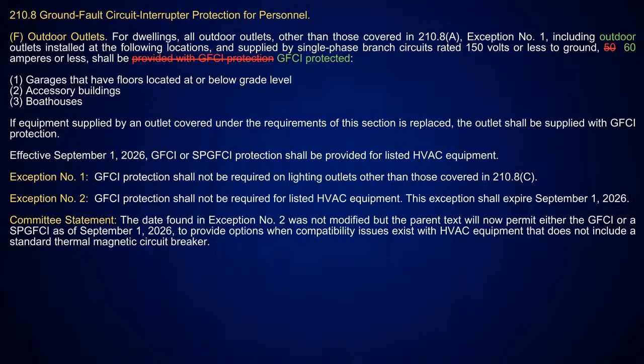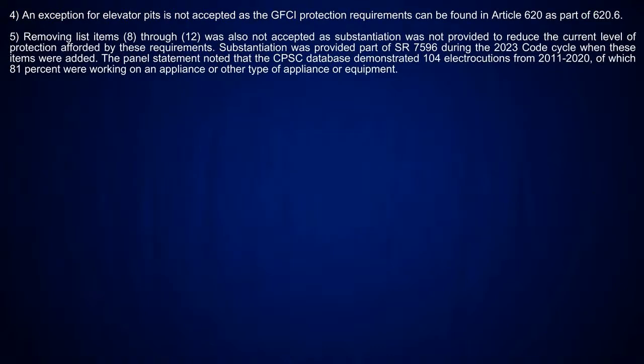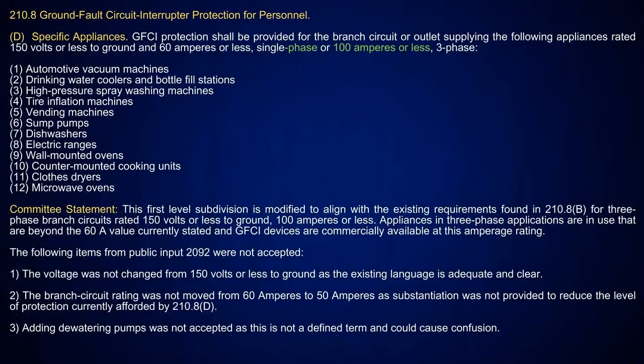So if you go back to that last slide, look at the drinking water cooler and bottle fill stations. So if this is in chapter 2, this is supposed to be protecting the branch circuit. But then all of a sudden you get your drinking fountain water cooler bottle fill stations, and they have internal GFCI. Now all of a sudden you don't have to protect the branch circuit anymore. Why is that? Why do you have that one exception just for that, but not all these other things?